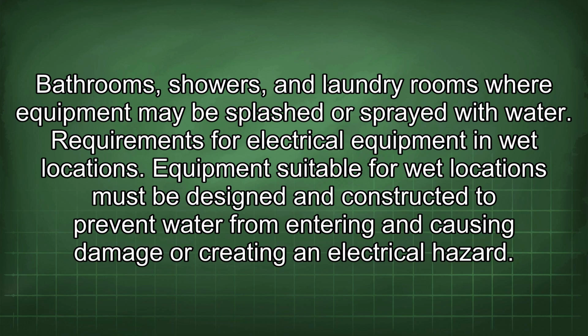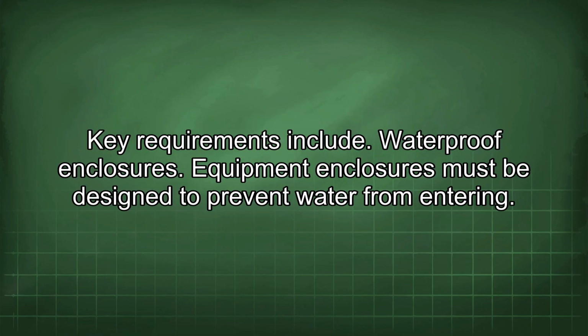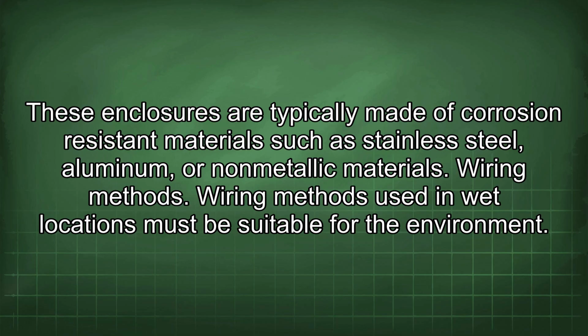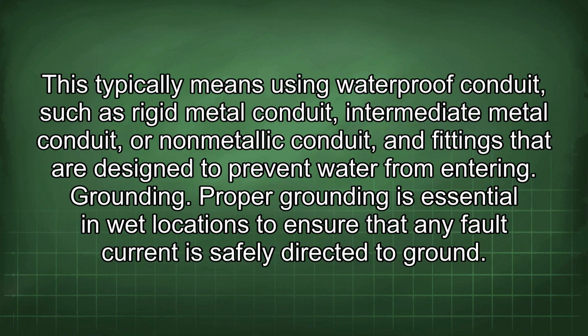Requirements for electrical equipment in wet locations. Equipment suitable for wet locations must be designed and constructed to prevent water from entering and causing damage or creating an electrical hazard. Key requirements include waterproof enclosures. Equipment enclosures must be designed to prevent water from entering. These enclosures are typically made of corrosion-resistant materials such as stainless steel, aluminum, or non-metallic materials. Wiring methods. Wiring methods used in wet locations must be suitable for the environment. This typically means using waterproof conduit, such as rigid metal conduit, intermediate metal conduit, or non-metallic conduit, and fittings that are designed to prevent water from entering.